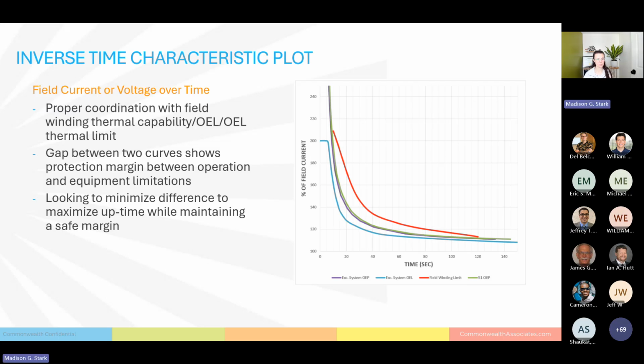One of the challenges here is to minimize that margin between your limiter, your protection, and then your field winding limits, because you want to keep your generator up as much as possible. That's the best case scenario for the grid, for your generator, for everybody involved. You really want to keep pushing power. But you also want to protect your generator. So it's kind of a balance of how do you minimize downtime while ensuring that you have the appropriate safety margin. And this is where it's a little bit of art as well as science, because every situation is going to be different. You have to account for your relay timing, you have to account for trip timing, and all of these other factors when you're looking at this timing margin. So it's going to be different for every system, but there are standard guidelines and criteria for what this margin should look like overall.